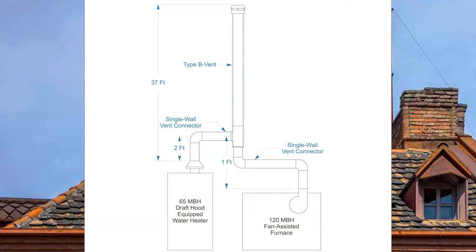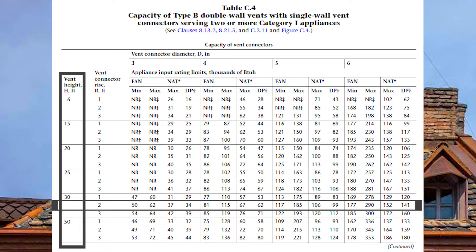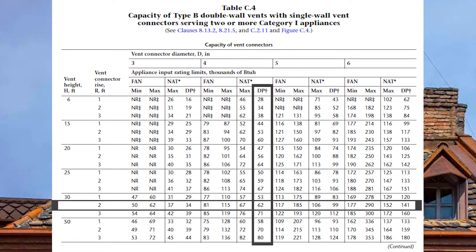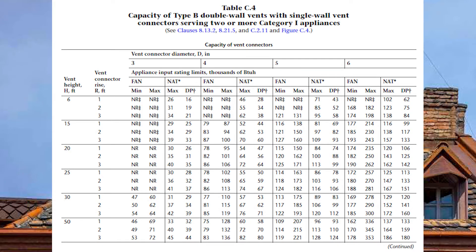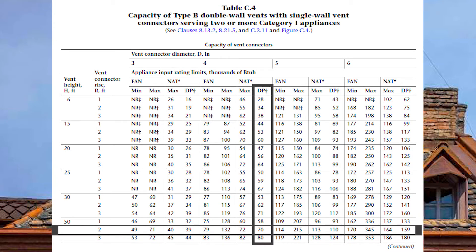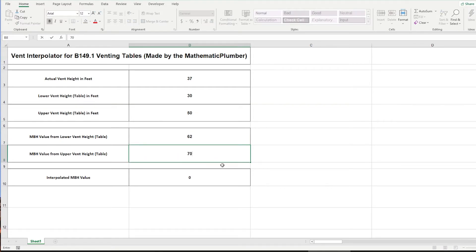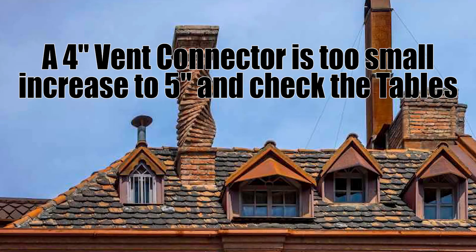Let's size the vent connector for the draft-hood-equipped water heater at 65 MBH. At the 30-foot vent height across on a 2-foot vent connector rise, Nat DP for 4 inch is good to 62,000 BTUs. At the 50-foot vent height with a 2-foot rise, 4 inch is good to a Nat DP of 70 MBH. Plugging 62 and 70 into the calculator gives an interpolated value of 64.8 MBH — slightly too small, so we bump up to 5-inch for the vent connector as well.